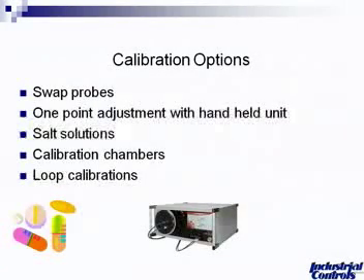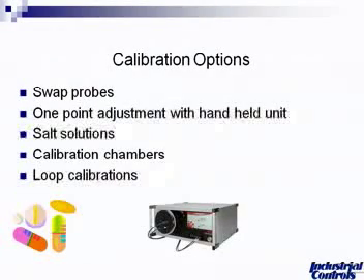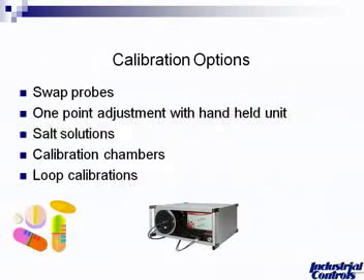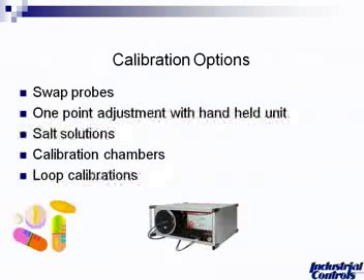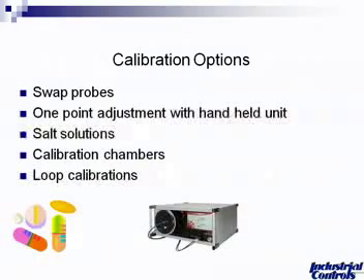The last item is loop calibrations. You may have all the confidence that your sensor is fully calibrated and accurate, but what about your digital or analog signal going back to your DCS data acquisition system or chart recorder? With digital technology now available, fixed simulators can be certified and used as a handy tool after you calibrate your probe. You use a fixed simulator to simulate a signal of humidity and temperature throughout your entire loop — so if you have a 50% RH simulator, your digital screen or chart recorder better be recording 50%, or else there's something else wrong along the way.